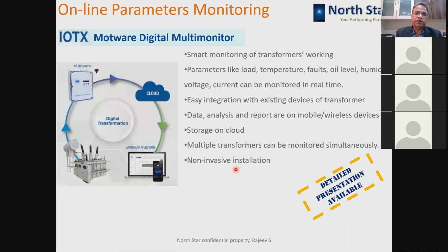Okay, then the IoTX Motoware digital multi-monitor system we have from Motwane. It is a smart monitoring of transformers. Working parameters you can cover like load on the transformer, what is the temperature of the transformer, if any fault is coming, any tripping is happening, what is the oil level in the conservator, what is the humidity level inside the transformer, how much voltage and current is there.